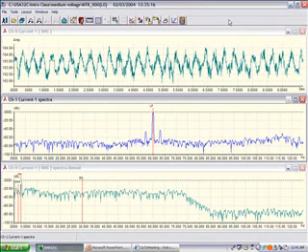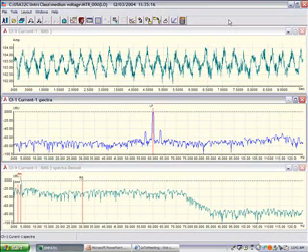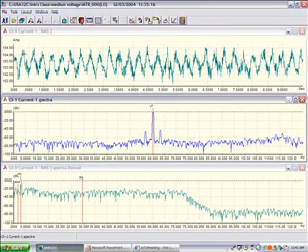How I used to check for broken rotor bars when I was in the field service industry many years ago was actually using an analog amp meter, not the new digital ones. It had to be a true analog meter, and literally watching the needle, and if I connected up to the cable of a motor that had a broken rotor bar, I would see a regular ticking action. And that would occur just like this waveform that you're looking at here.